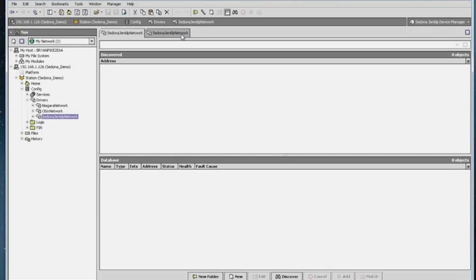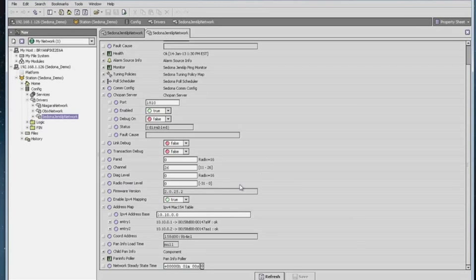In troubleshooting a network, if you have problem with Sedona devices and you're not sure if it's the Sedona network giving you issues or the wireless, this is where you would go back and look and see if the devices are online. OK obviously means they're online and communicating. If they're offline, you'll have a negative or a dash.